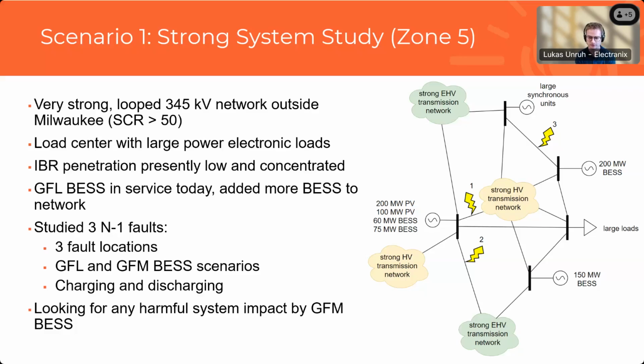And the region we looked at can be characterized by a strong 345 kV network. If we want to quantify strong, the short circuit ratios in the region were kind of above 50. This region featured large synchronous machines and large loads. The IBRs in this model were a mix of existing and planned IBRs. And as Andrew mentioned, we threw a couple more fictitious planned grid forming or battery plants into the system.